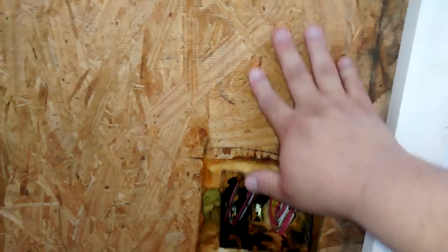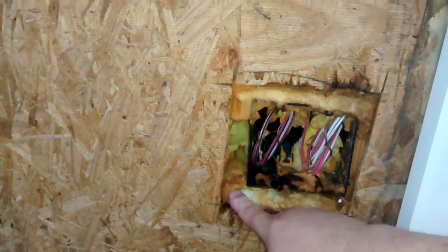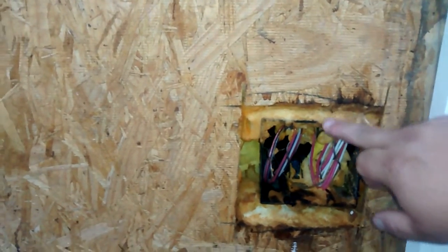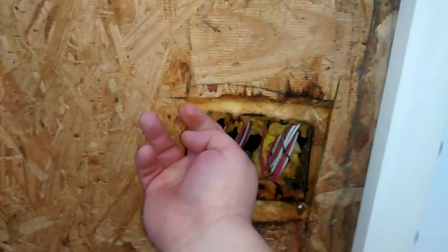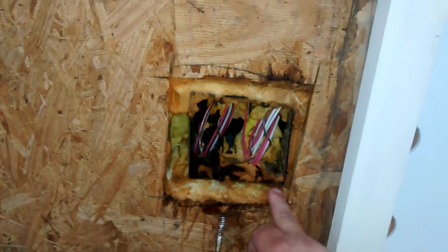But you'll also note that there is no water dripped down on the wall above it. In other words, this water is coming from inside the wall. It's not surface water that's soaked into the spray foam here, but the inside of the wall is actually wet, and the open cell spray foam insulation is saturated.